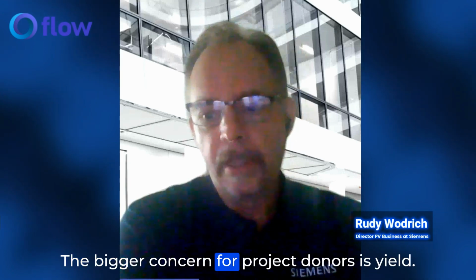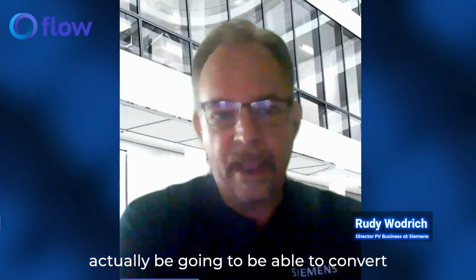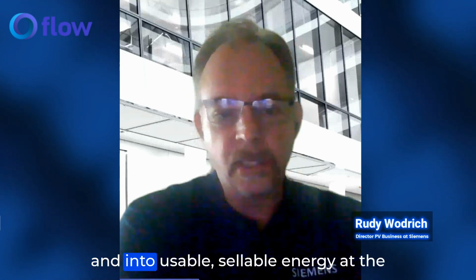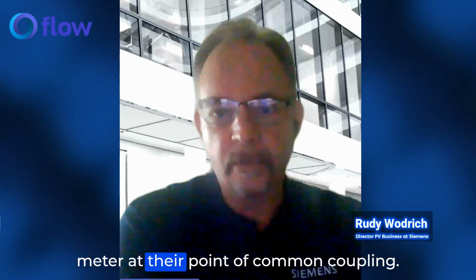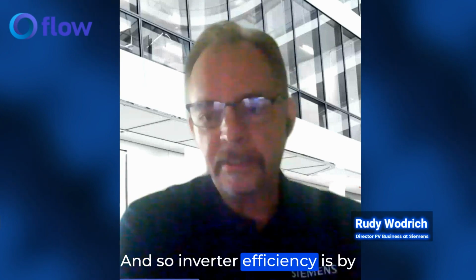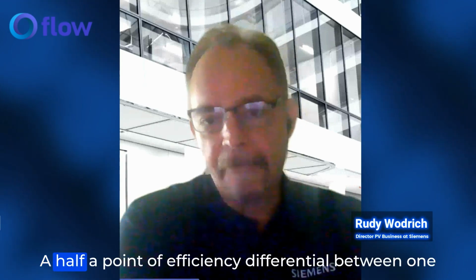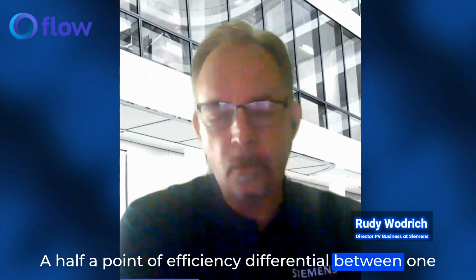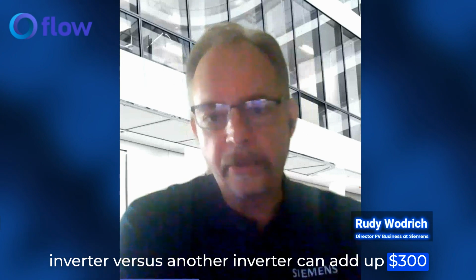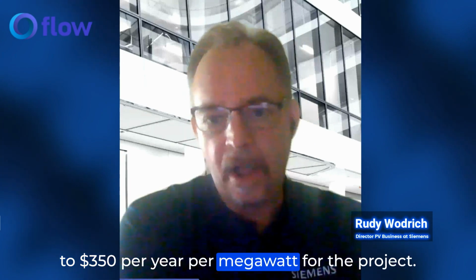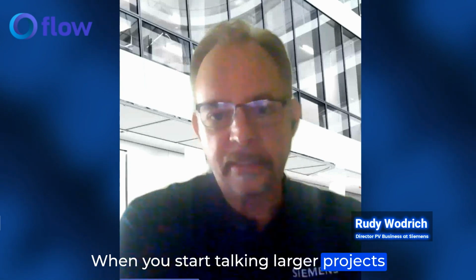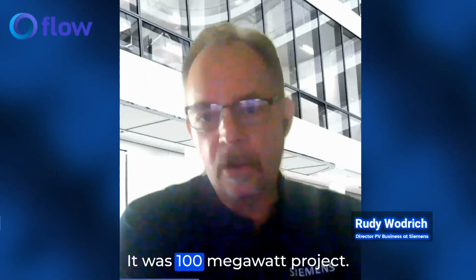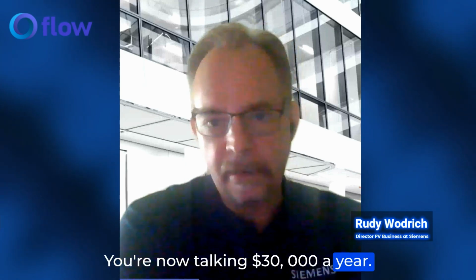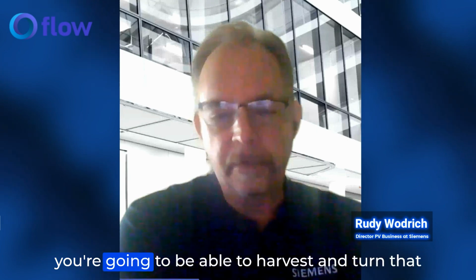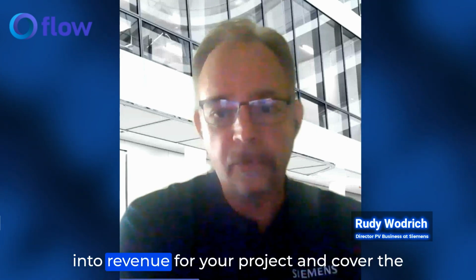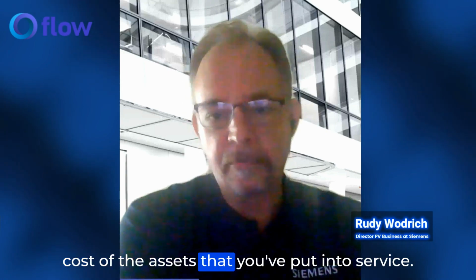The bigger concern for project owners is yield—how much energy they'll be able to convert into usable, sellable energy at the meter, at their point of common coupling. Inverter efficiency is by far the biggest factor there. A half a point of efficiency difference between one inverter and another can add up to $300 to $350 per year per megawatt for the project. So with larger projects, this adds up fairly quickly—on a 100 megawatt project, you're talking about $30,000 a year. This affects how much energy you can harvest and turn into revenue, covering the cost of the assets you've put into service.